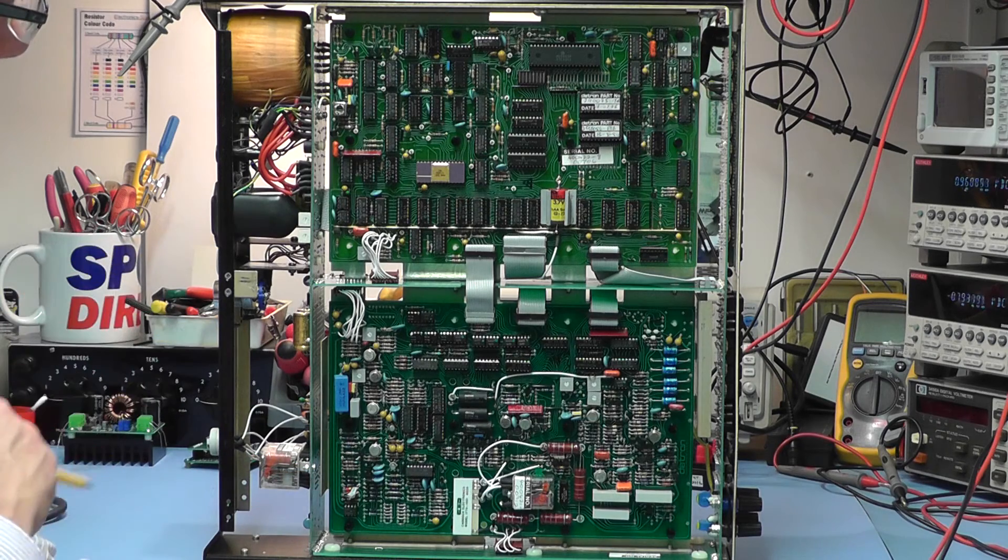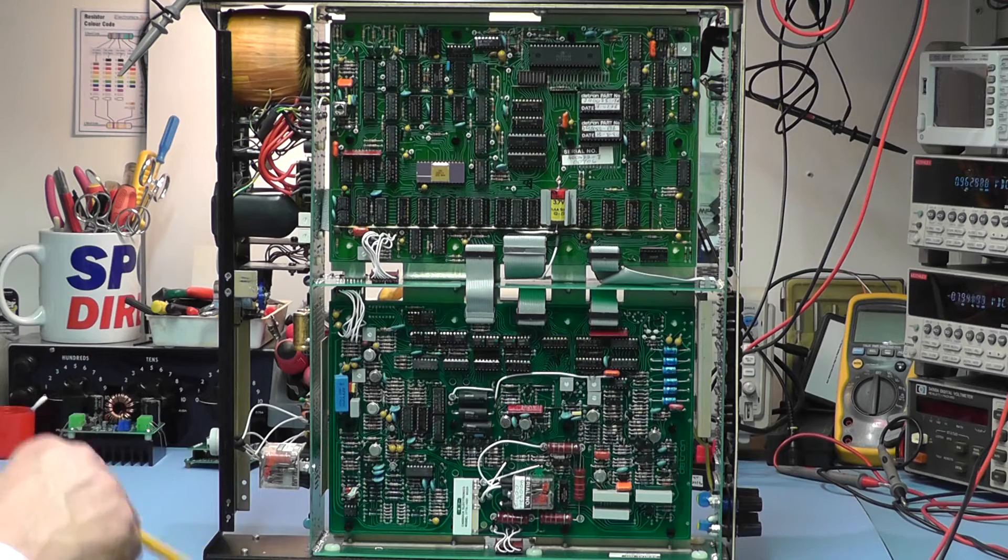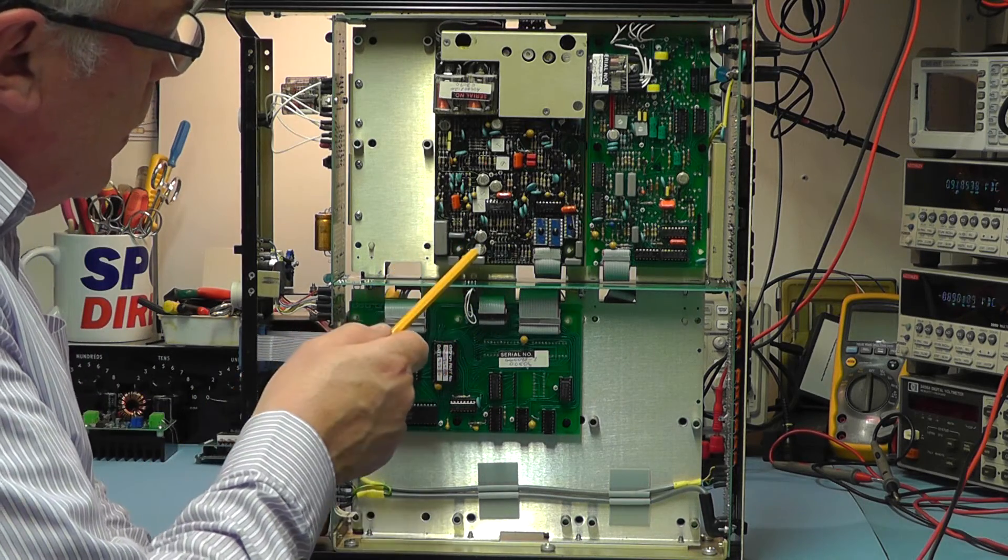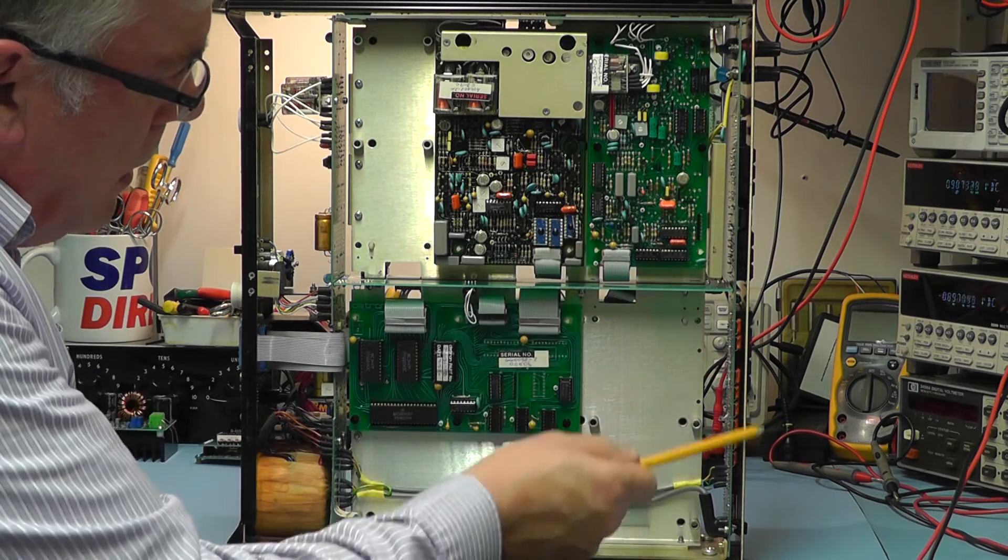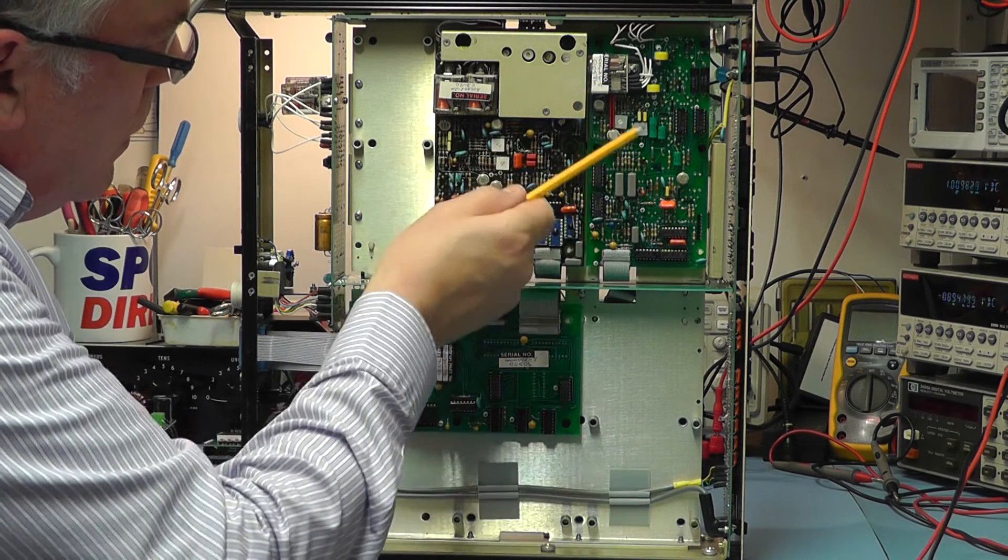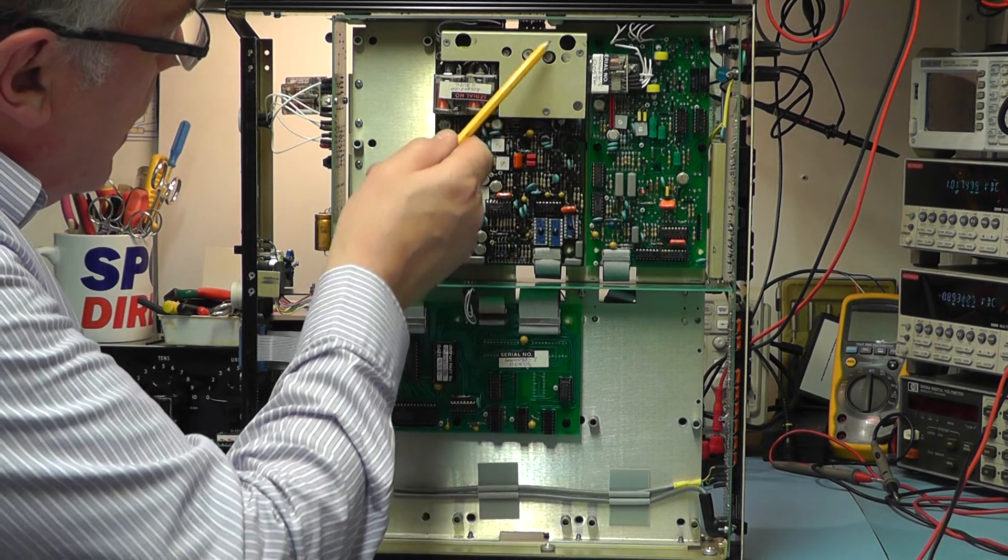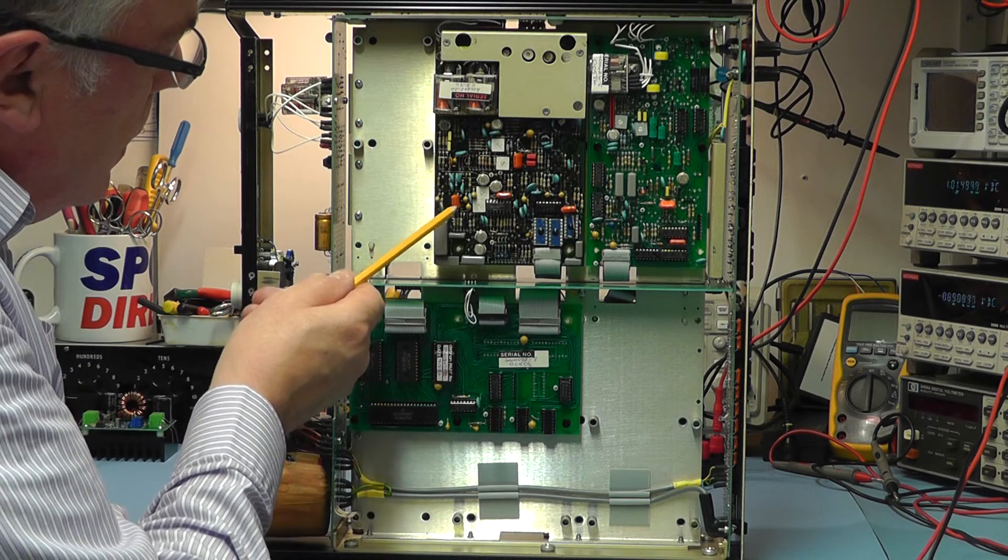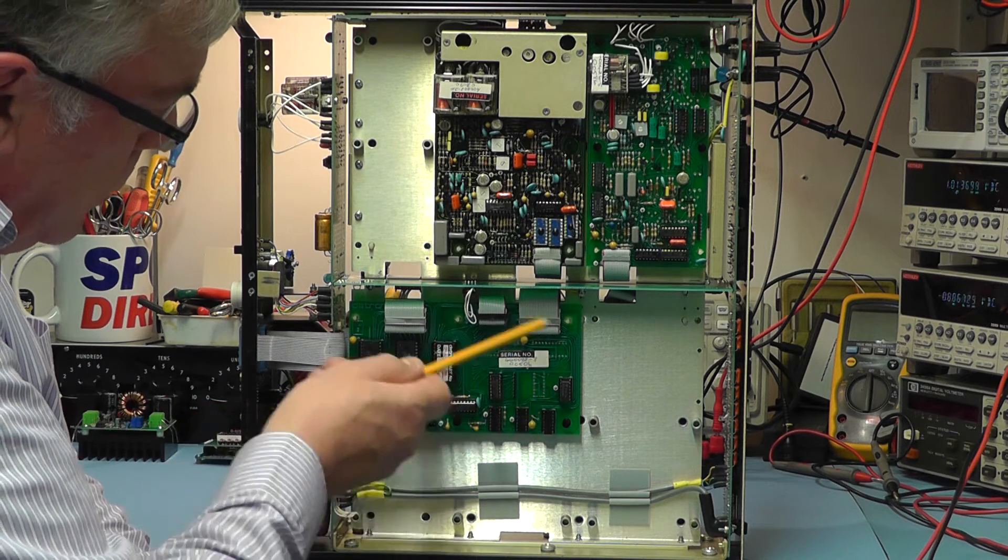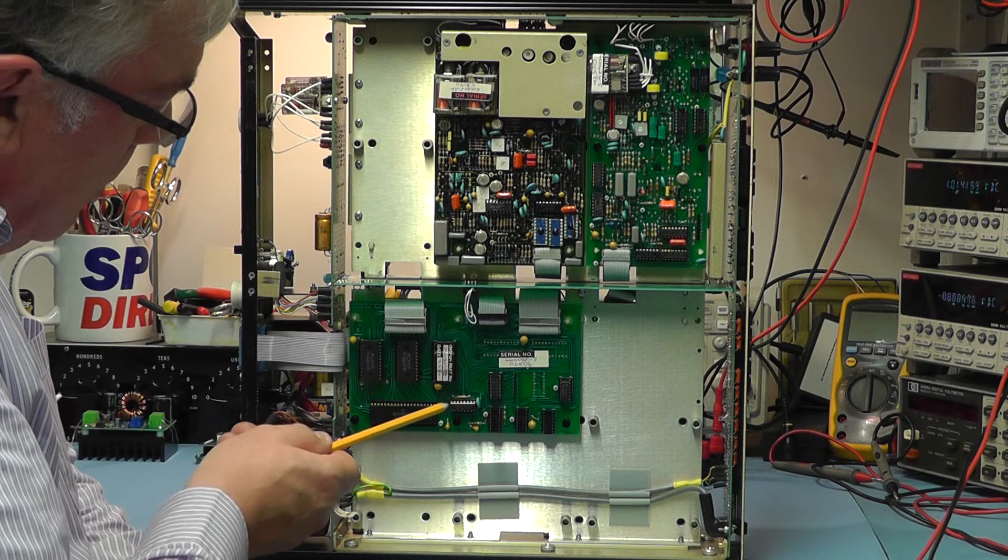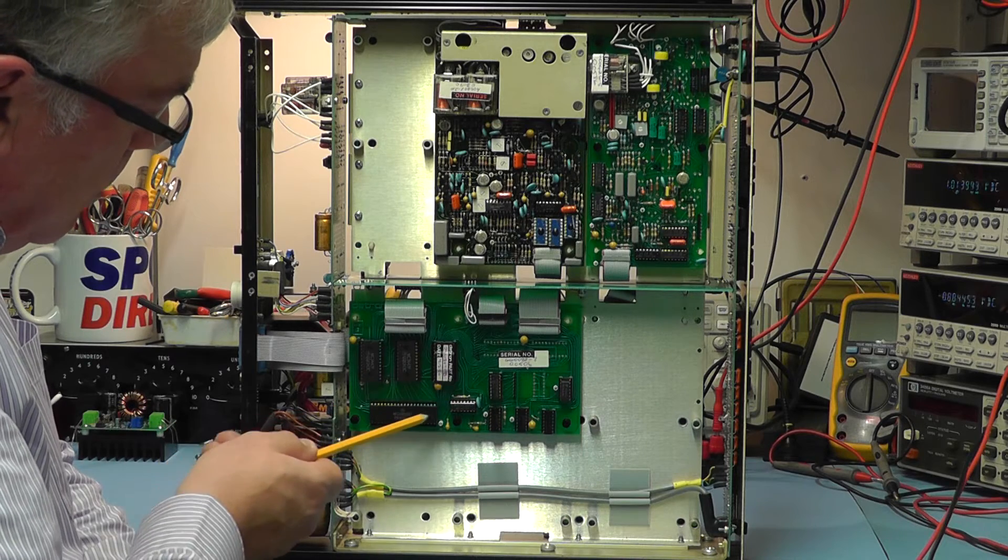Okay let's turn it around and let's have a look at the other side, the underside of the meter. Here you can see the modules on the underside of the meter. There's the front panel again that side. We have two modules here at the top. The module here at the front is the resistance module and the unit behind it here is the AC voltage module. Below we have one module here which is the GPIB, IEEE 488 interface board.